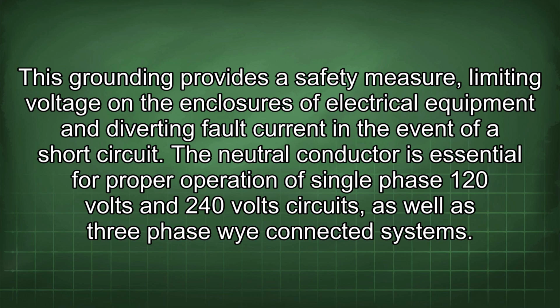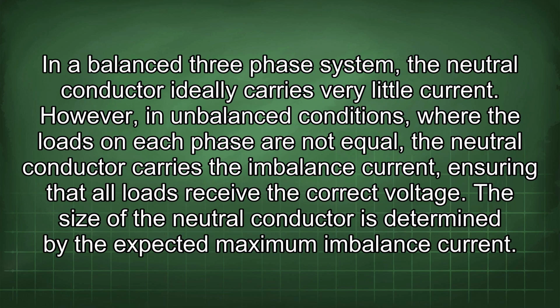The neutral conductor is essential for proper operation of single-phase 120 volt and 240 volt circuits, as well as three-phase Y-connected systems. In a balanced three-phase system, the neutral conductor ideally carries very little current. However, in unbalanced conditions, where the loads on each phase are not equal, the neutral conductor carries the imbalanced current, ensuring that all loads receive the correct voltage. The size of the neutral conductor is determined by the expected maximum imbalance current.